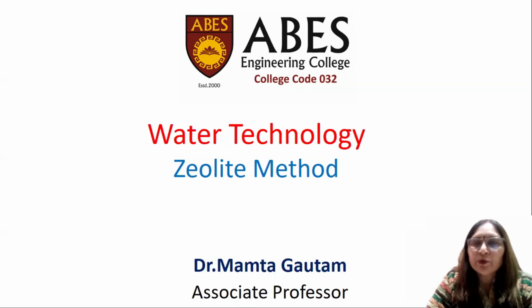Today I am going to discuss the water softening process, that is the zeolite method. In the previous lecture, we discussed hardness, types of hardness, degree of hardness, units of hardness, and boiler problems. Today, I will explain the water softening process, that is removal or reduction of the dissolved salts of calcium and magnesium.